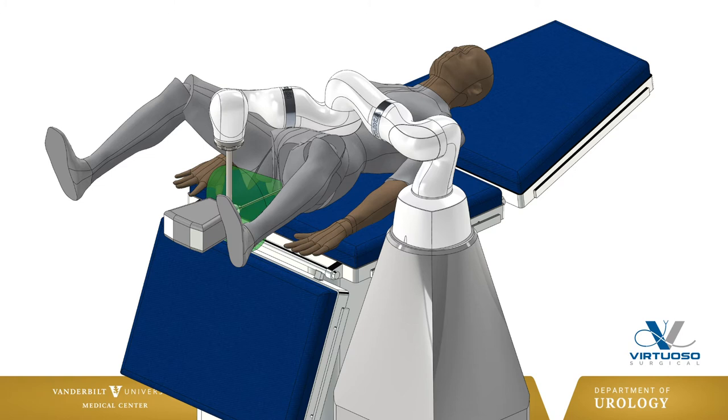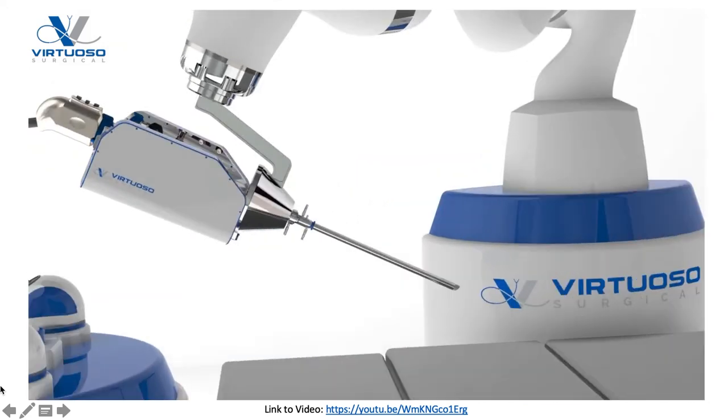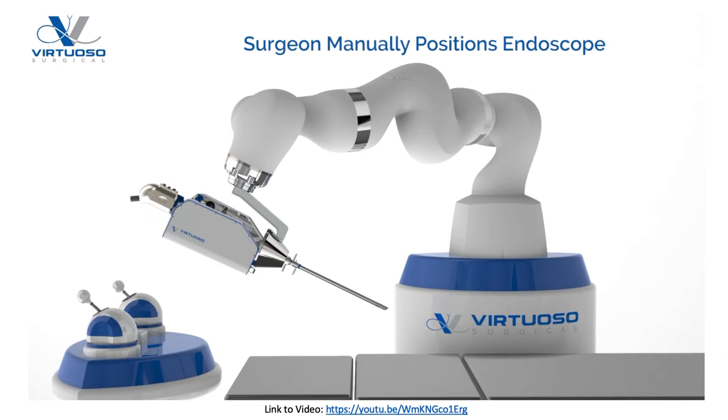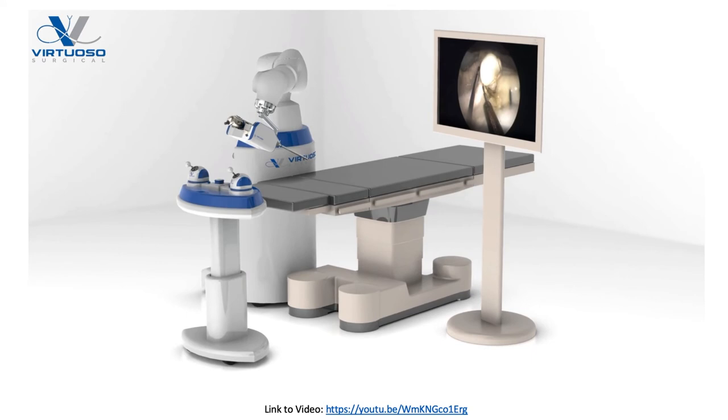How on earth would you keep that in a patient's urethra? We needed something that would be able to hold the instrument. This is called the KUKA robot — a German medical grade robot that essentially is not functioning autonomously; all it's doing is counterbalancing the weight of the robotic portion that's in the urethra. Here is the system as we would envision it when completely developed. You can see that the surgeon input console has been moved away from the patient — much like the Avicenna, you're going to be away from the patient.